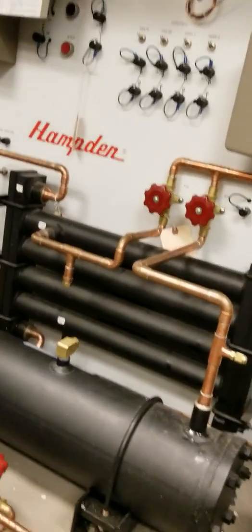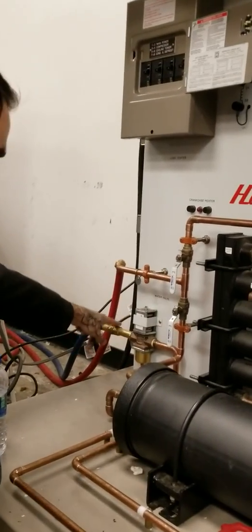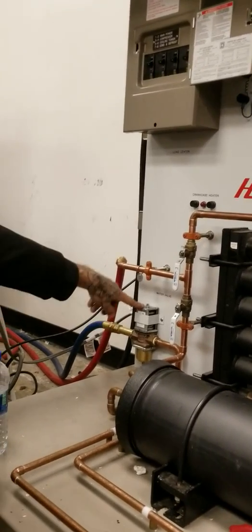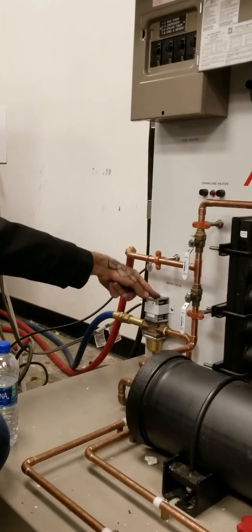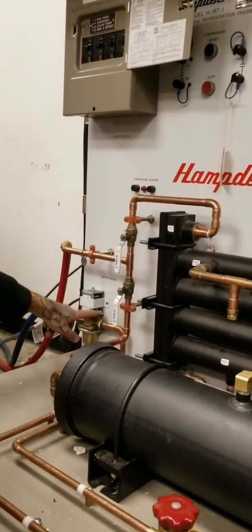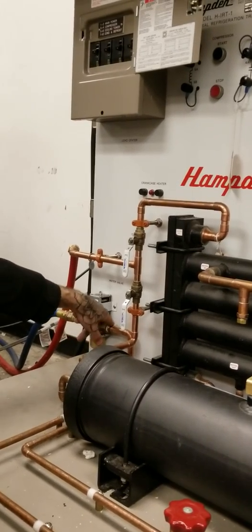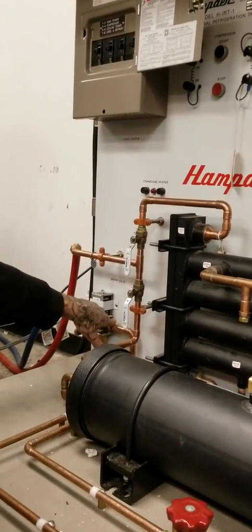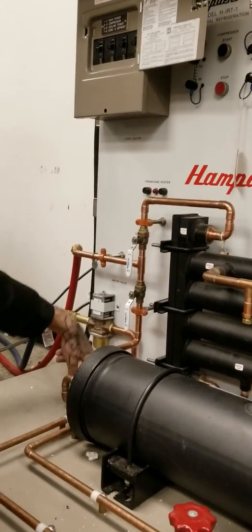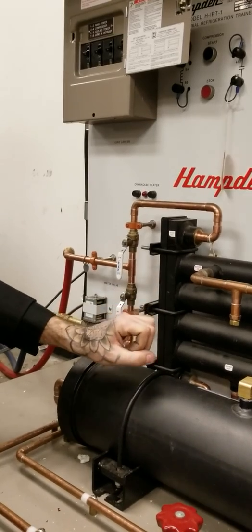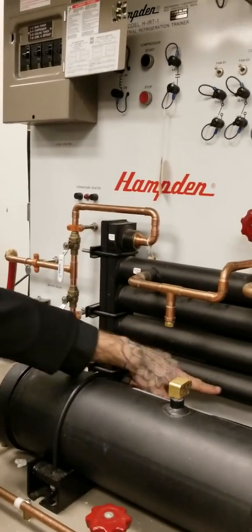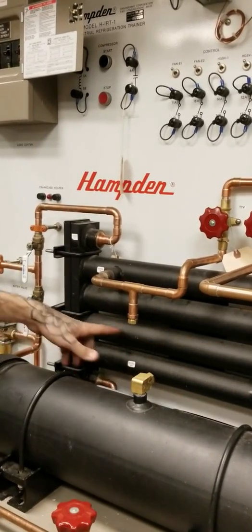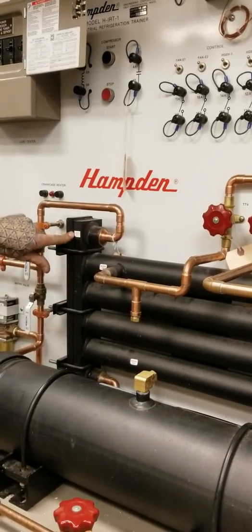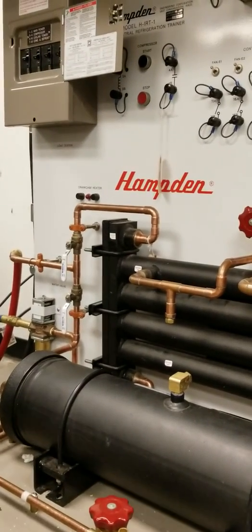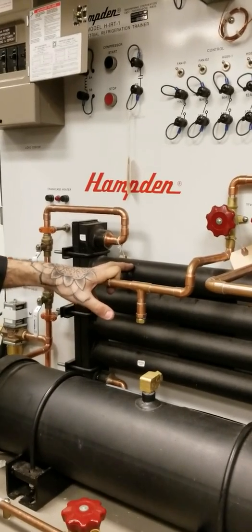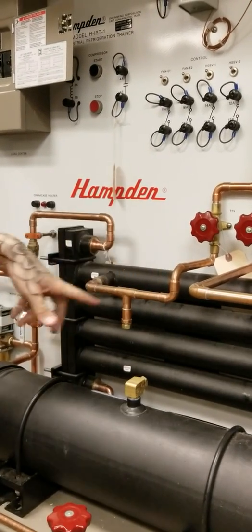So to create that, we have our water valve. This is a water regulating valve that you could control the amount of GPM, gallons per minute, that flows through our heat exchanger. The way that works is if we just put it right into the shell, we're going to mix refrigerant and water, right? That would be bad. So what we have is this water comes in through the bottom and it stays in a tube the whole time. It's running through the middle of these bigger black tubes. You have a copper tube running through there, and then that tube U-turns and comes all the way until the water leaves out of here. So the water and the refrigerant never make direct contact, but they will be having heat exchange because that cold water is going to be flowing through the tube.